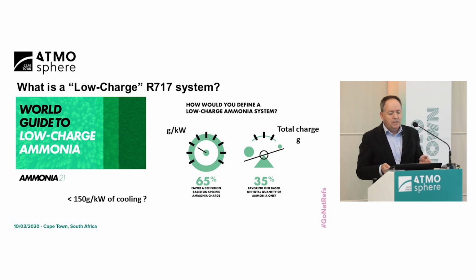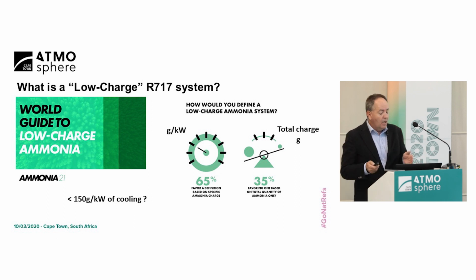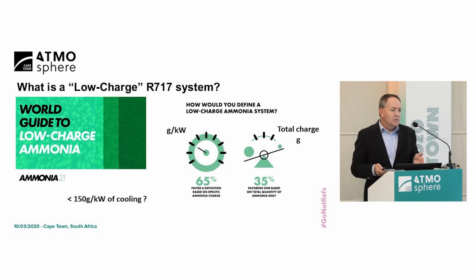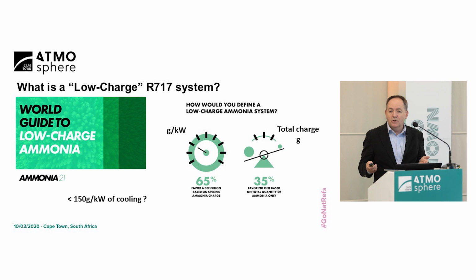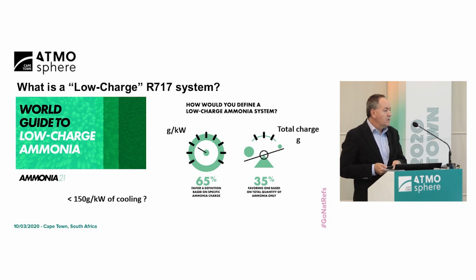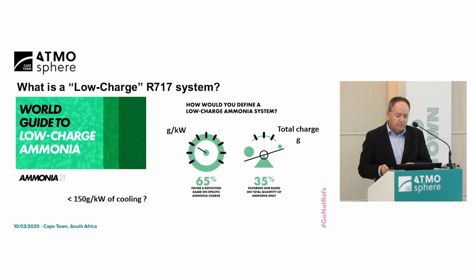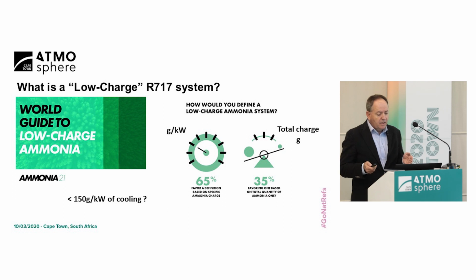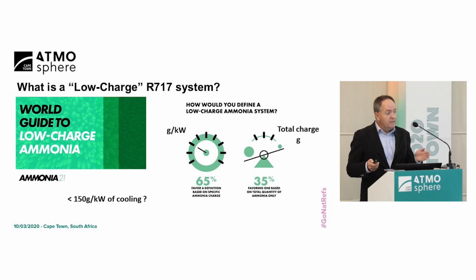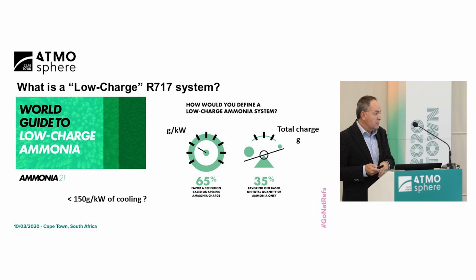So you can look at it in terms of grams per kilowatt of cooling, but of course you operate at different suction temperatures. So if you refer to kilowatts, what are you referring to? -10, -30? So it's difficult to define. The alternative is to refer to the charge, similar to the hydrocarbon solutions. And basically, I think what comes from your document more recently is you consider it low charge if it's smaller than 150 grams per kilowatt.